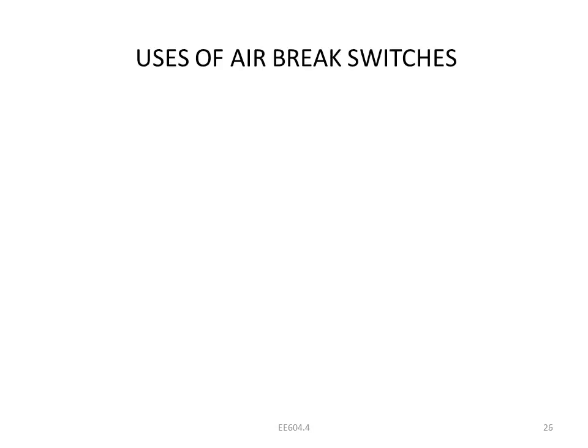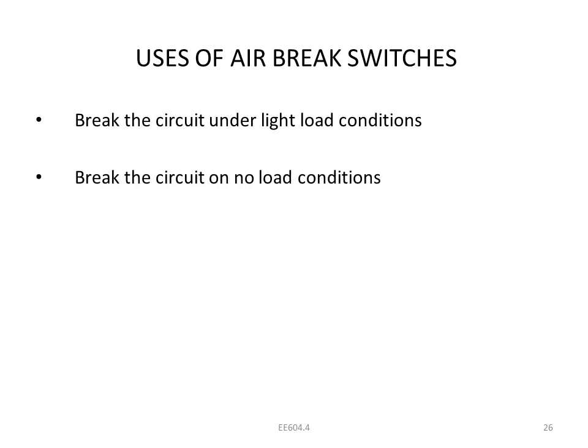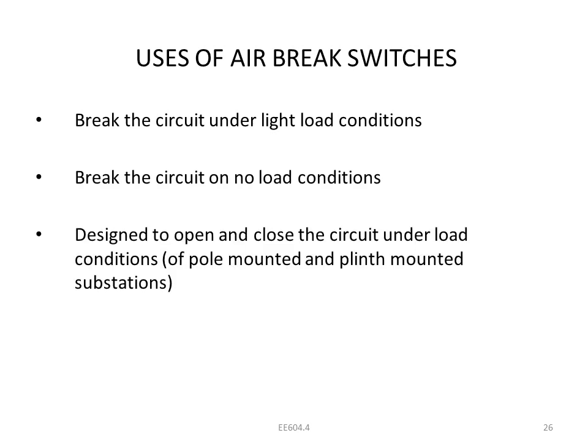And the use of air break switches: an isolator will be used for no-load conditions only, while an air break switch is designed to open and close the circuit under load conditions. Okay, that's a different thing, right? So the isolator is for no load, and this is for the under-load condition.